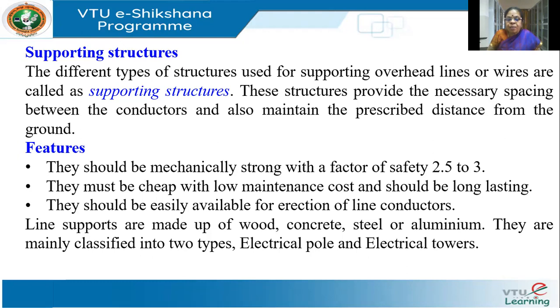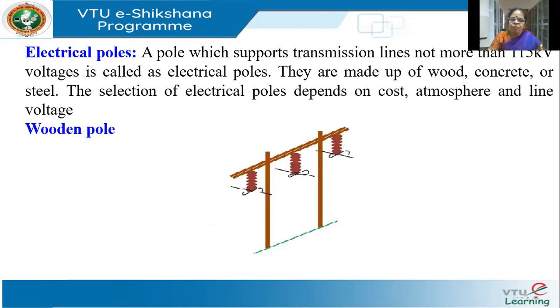The materials for poles and support structures can be wood, concrete, steel, or aluminium. Electric poles support transmission lines up to 115 kV — more than that, we use towers. One of the most popular historical materials are wooden poles. Though not very common in India now, they are used for short spans up to 50 meters in distribution systems, especially in rural areas where wood is easily available. Wood is an insulating material, so it causes less flashover.